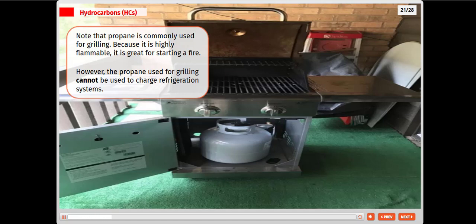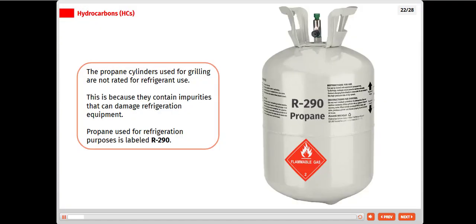Note that propane is commonly used for grilling. Because it is highly flammable, it is great for starting a fire. However, the propane used for grilling cannot be used to charge refrigeration systems. The propane cylinders used for grilling are not rated for refrigerant use. This is because they contain impurities that can damage refrigeration equipment. Propane used for refrigeration purposes is labeled R290.